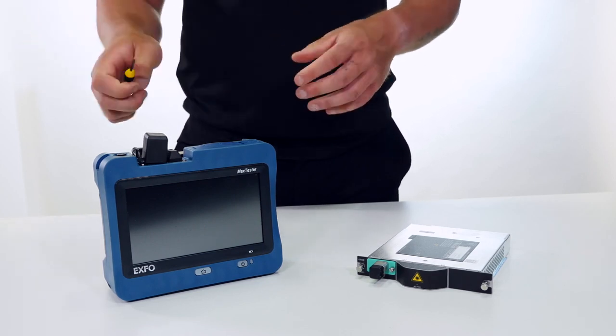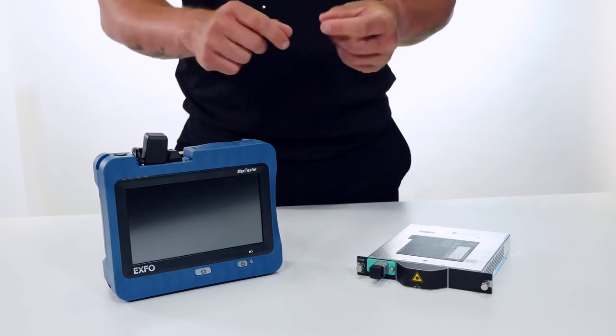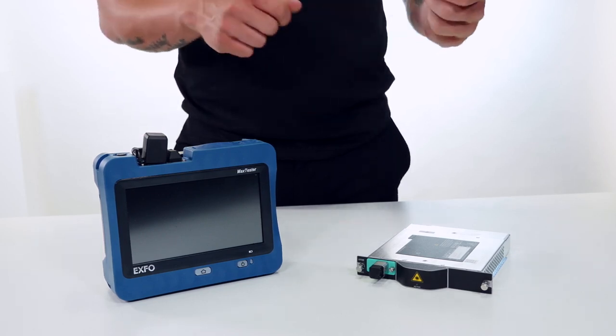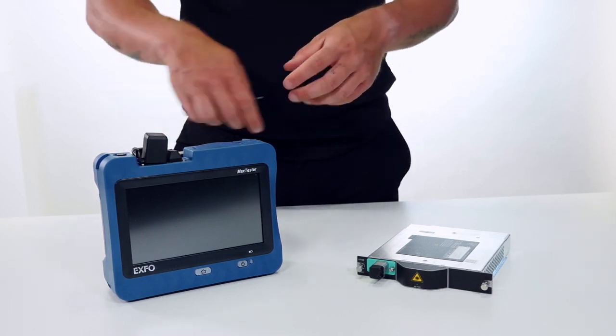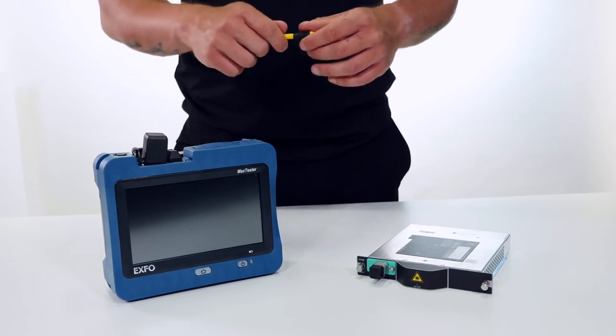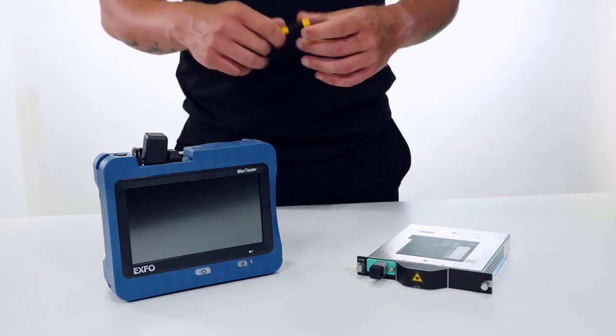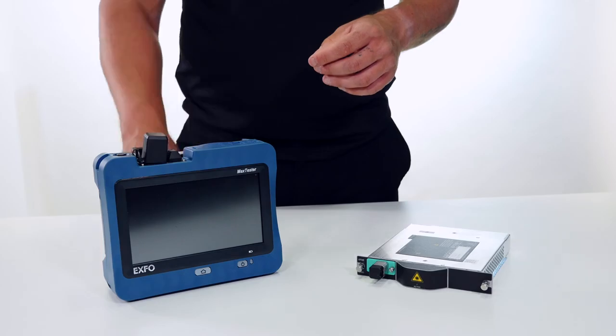For this reason we don't want to do multiple changes from UPC to APC, UPC to APC. If we change the connector every day we're going to end up damaging the internal connector which requires a recalibration.